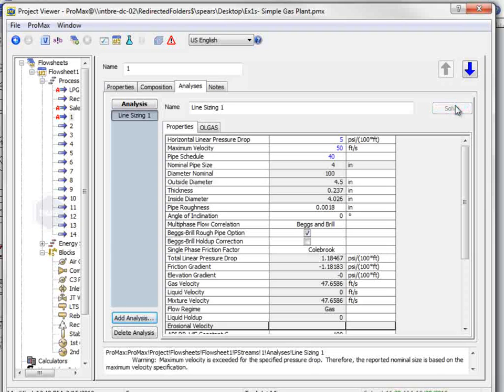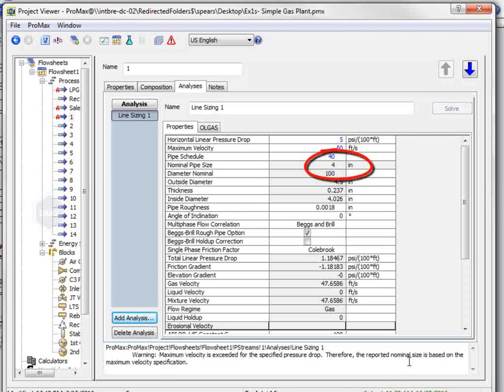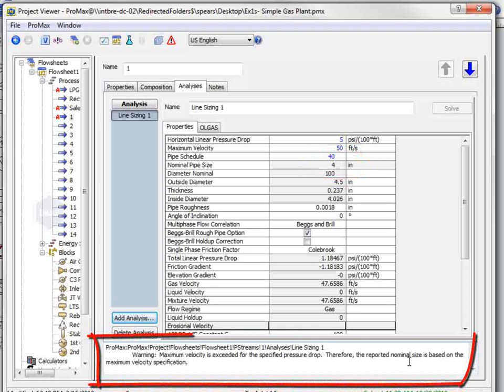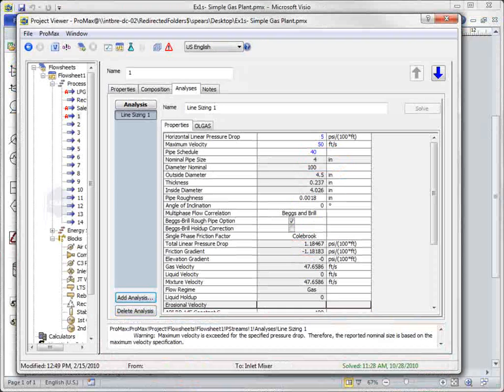the new required size is a 4-inch pipe. ProMax also gives us the warning stating that it is the velocity requirement that is limiting the size required from the pipeline.